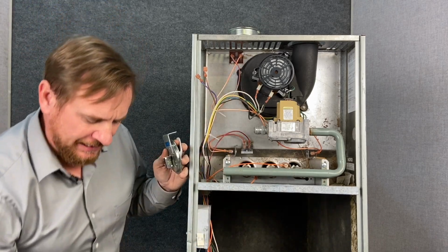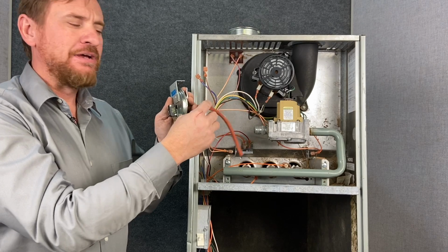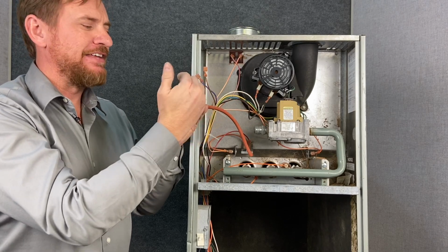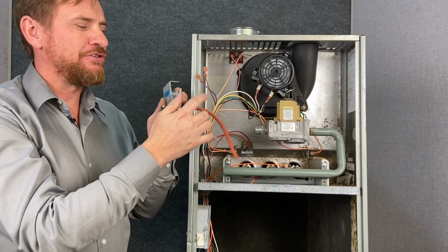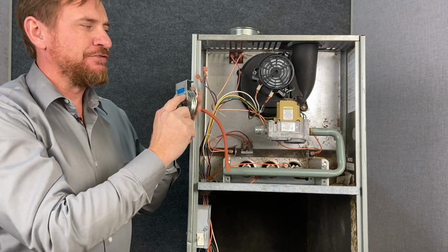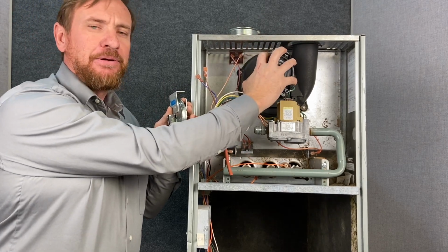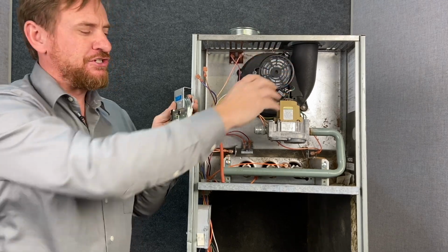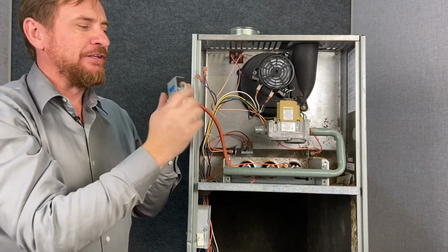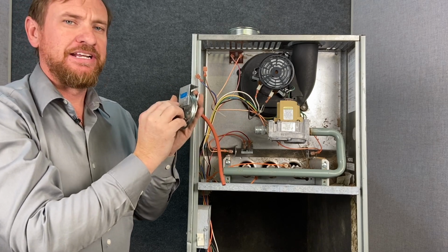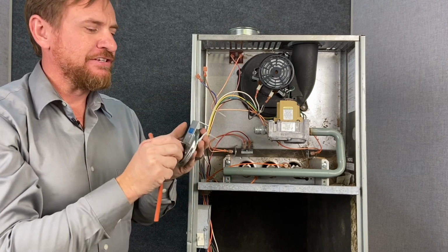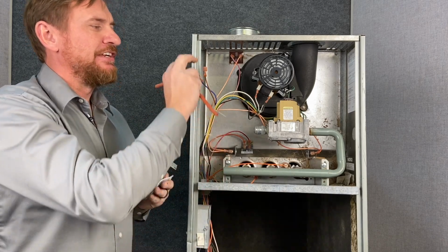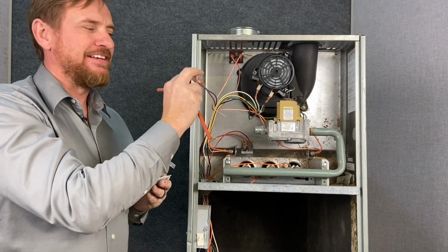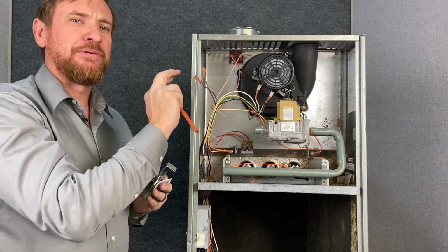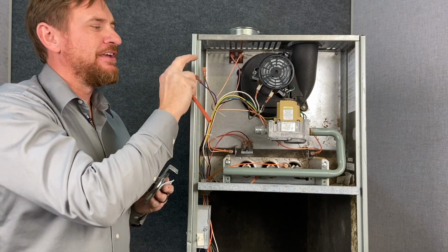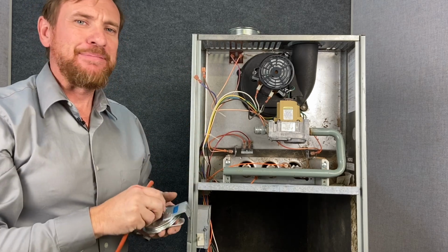So we could actually put a T on this tube, and we could measure how much pressure we have, negative pressure or vacuum we have going to this pressure switch. If you don't have enough pressure for the switch to close, you need to be looking at the inducer motor. If you do have enough pressure for the switch to close and the switch is not closing, you need to be looking at the hose or this component here itself. So one of the things that's pretty easy to replace, and you can't bypass these. The IFC knows if you try to bypass this, it won't let it, because it knows it should only be open in the proper sequence and only closed in the proper sequence. So you don't bypass that, and really just don't bypass any safety components.